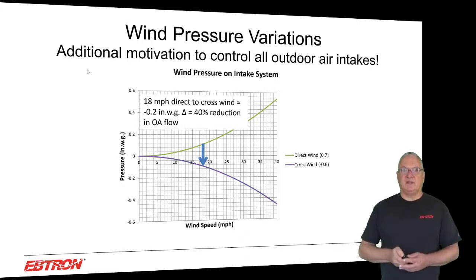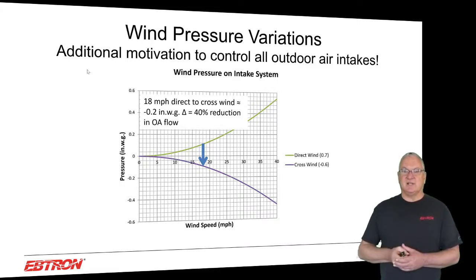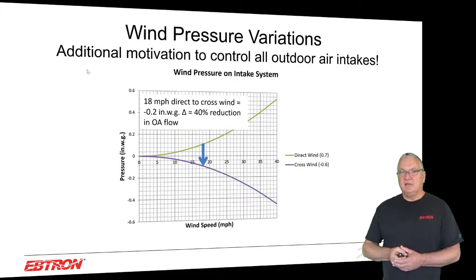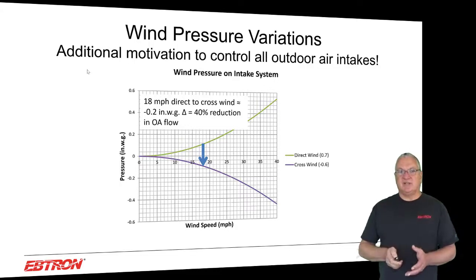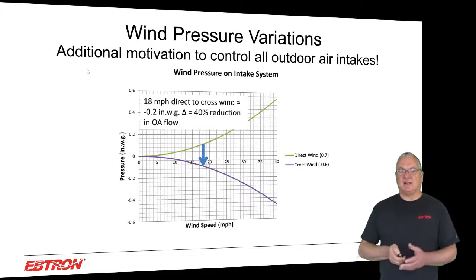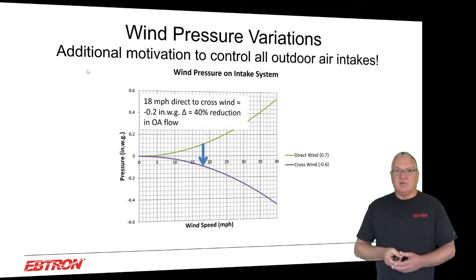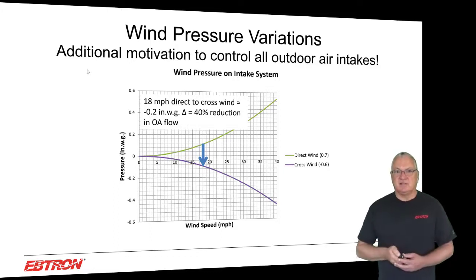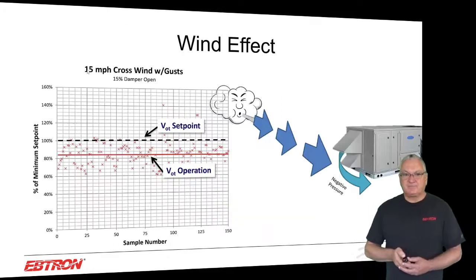In this example, if you operated the system with an 18 mile-per-hour direct wind, then checked the outside airflow when there was an 18 mile-per-hour crosswind — even if the fan speed was constant — you would see this two-tenths of an inch change and the same 40% reduction in outdoor airflow rate. This has nothing to do with fan speed changes. We've been trying to get people to understand this for a long time: it's not just fan speed changes you have to deal with. You have to consider the external environment as well.